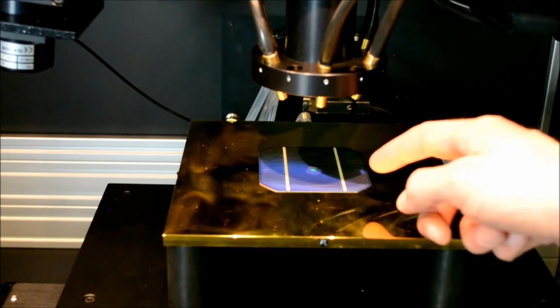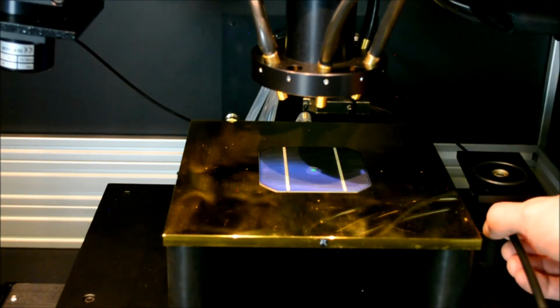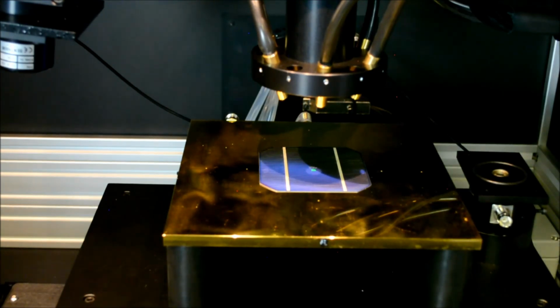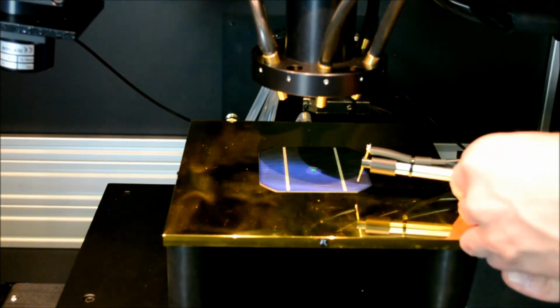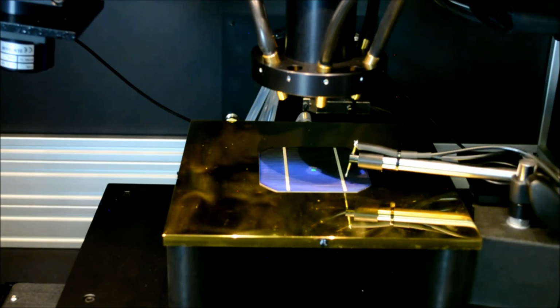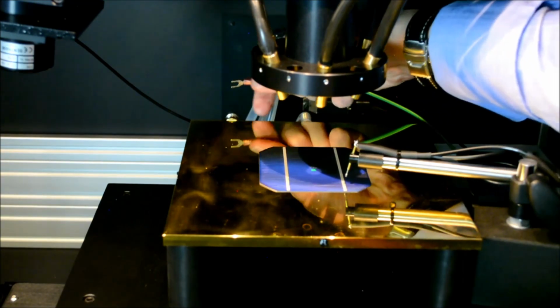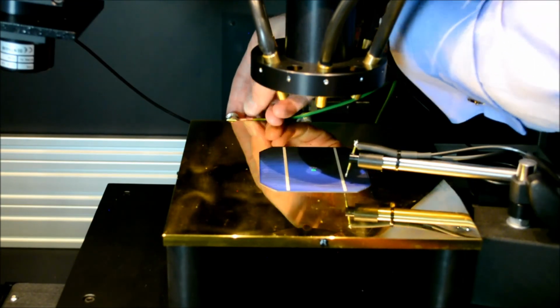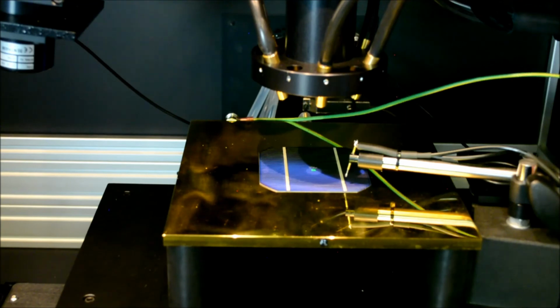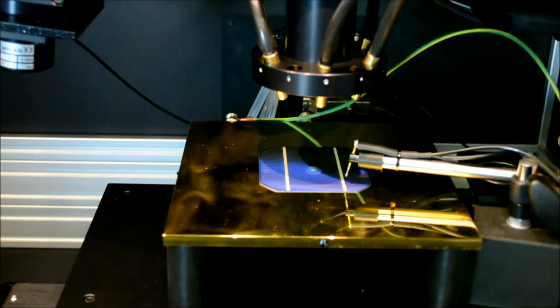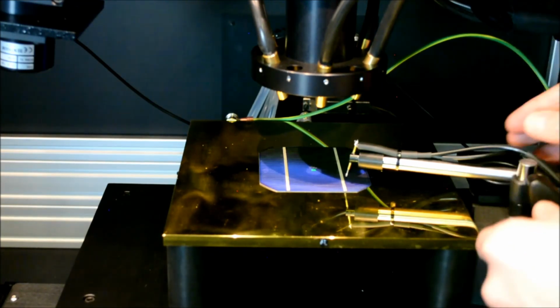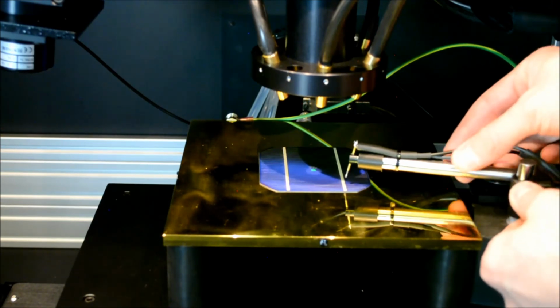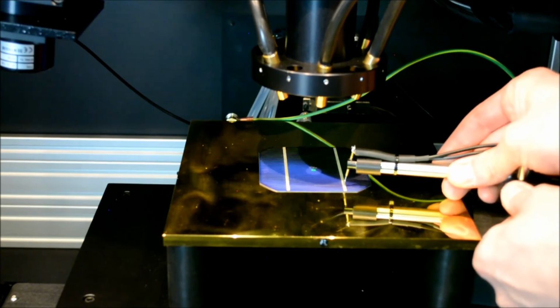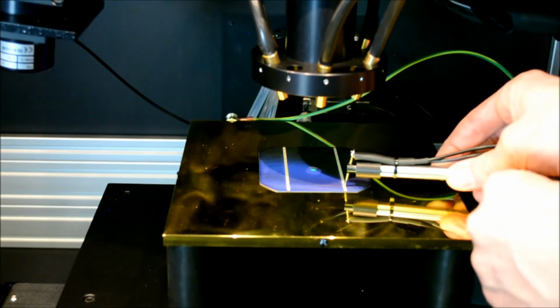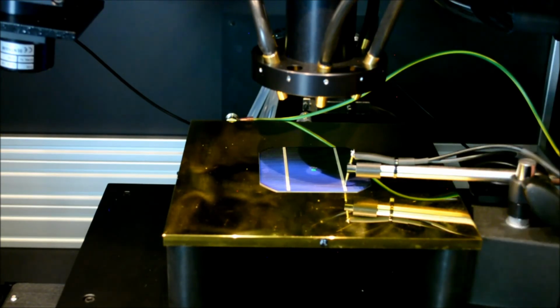With this top rear contact device, we can use a single probe to electrically connect to the device. So I position the probe on the right side of the temperature controlled vacuum mount. We connect the back plane of the mount using the mounting point to the rear and connect that to the mounting point on the probe. We can gently loosen the clamp of the probe and lower into position, locking it in place and also locking in the magnetic base in place.